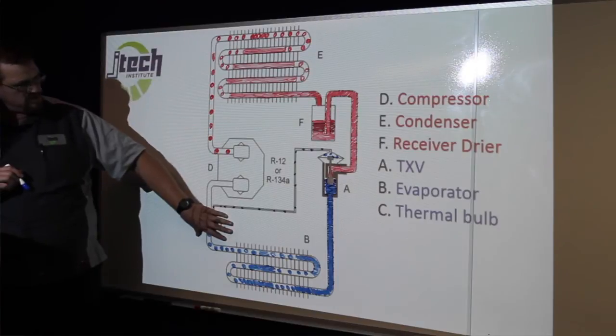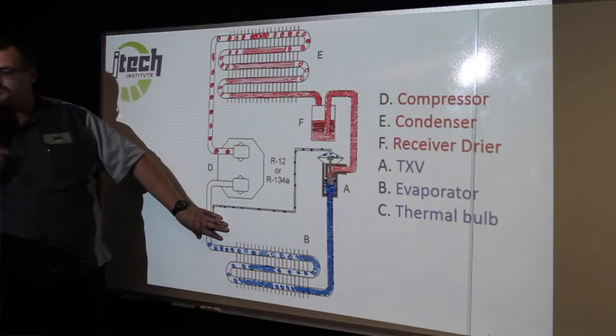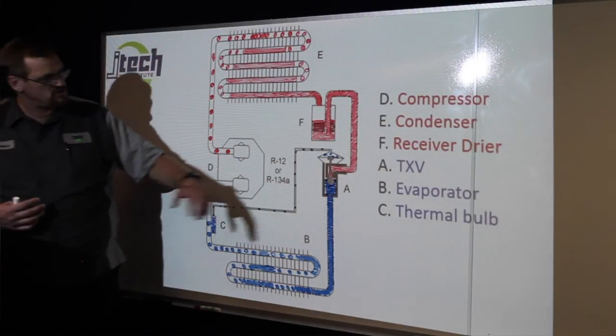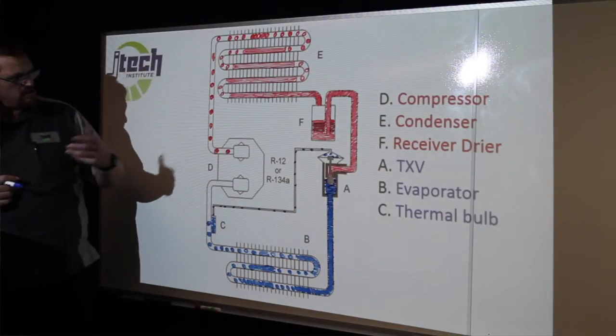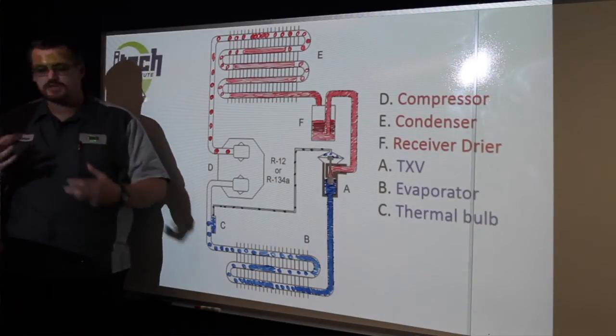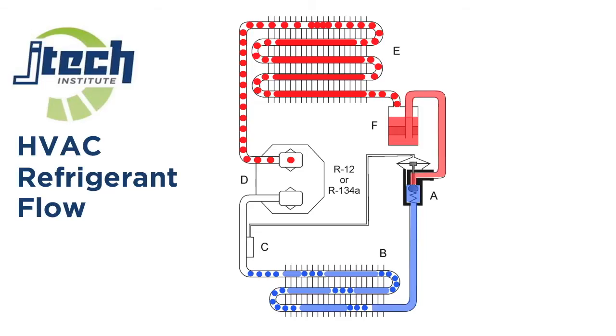By monitoring the tailpipe temperature, the TXV controls the quantity of refrigerant flowing. The higher the tailpipe temperature, the further the expansion valve will open. The colder the tailpipe temperature — such as when liquid may still be present — the further it closes down and restricts the flow. The spring is closing while the power head is opening. There is a balancing line internally, which is discussed more in refrigeration. The thermal bulb establishes proper flow and proper quantity of refrigerant, and from there the tailpipe feeds back to the suction side of the compressor, completing the flow.